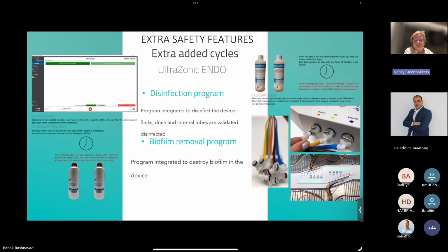The extra safety features we have here are because of the notified body that we got. We have to clean and avoid the growth of biofilm in the device, so in the sink. And this is also with these little bottles, with the traceability. The machine will give you an announcement the moment that you have to do the biofilm removal program, or when the program of disinfection has to be done. The machine is that smart, it will give you a sign that you have to do it.